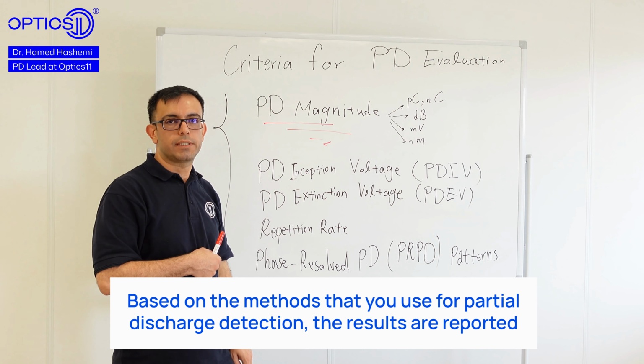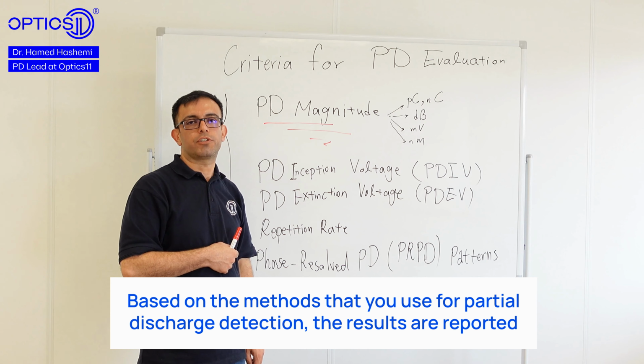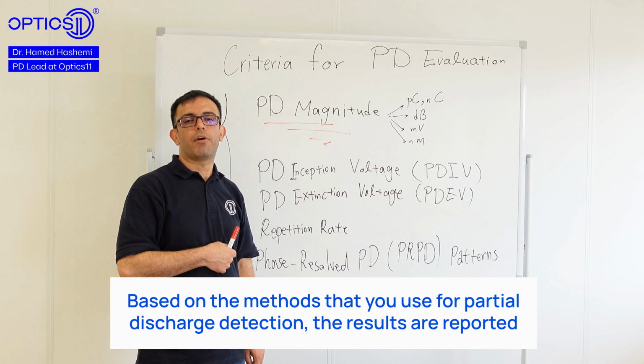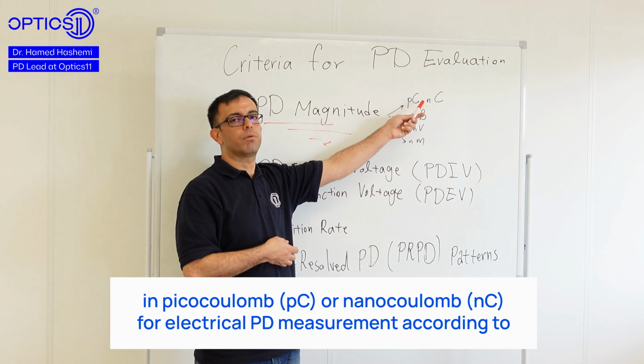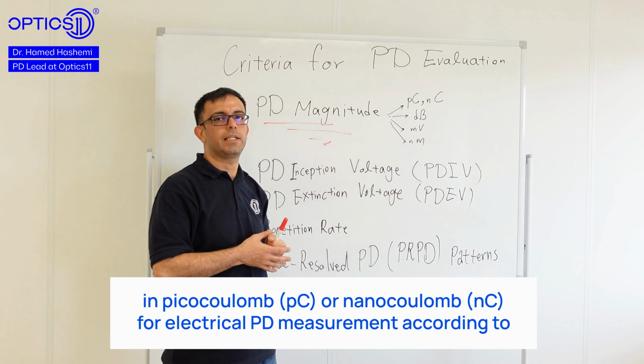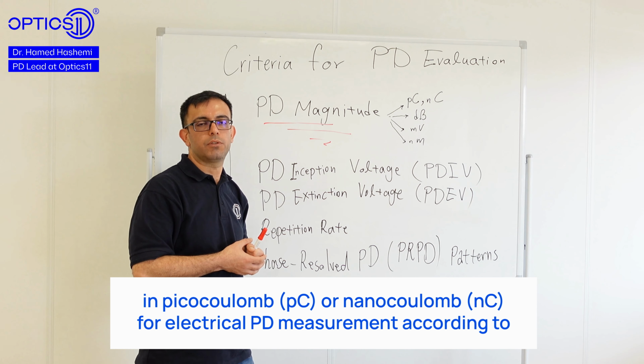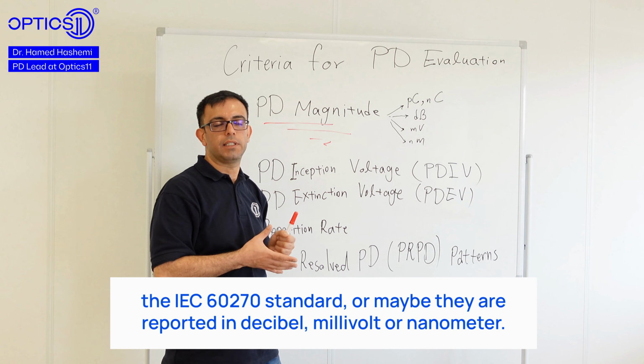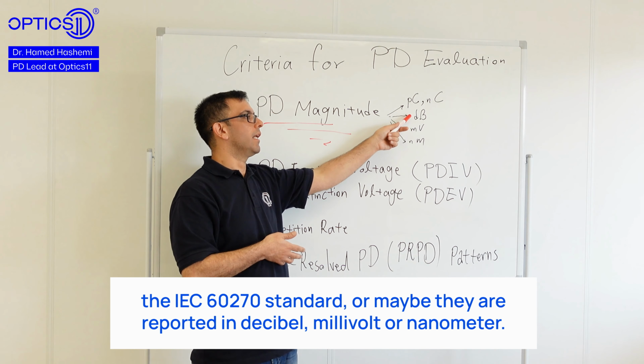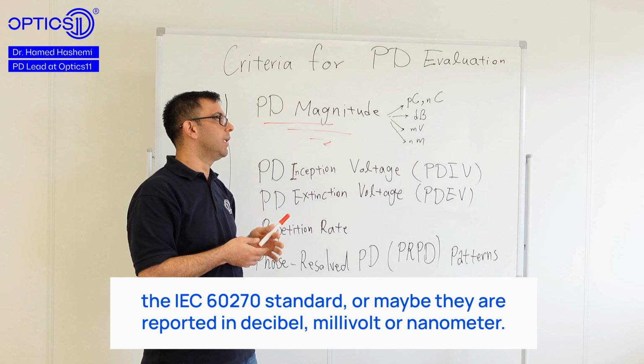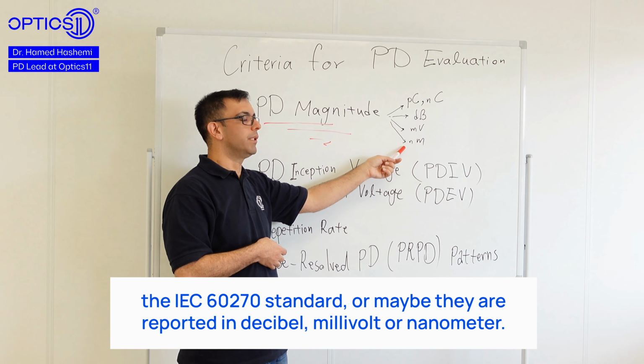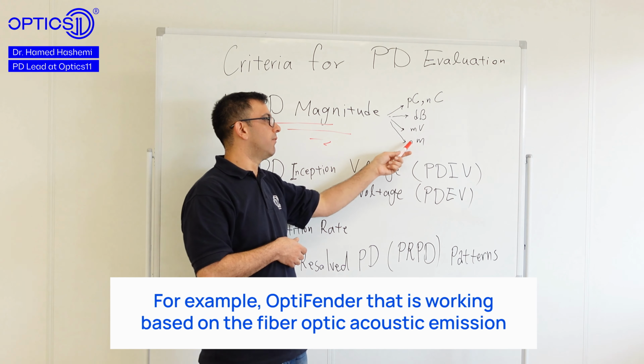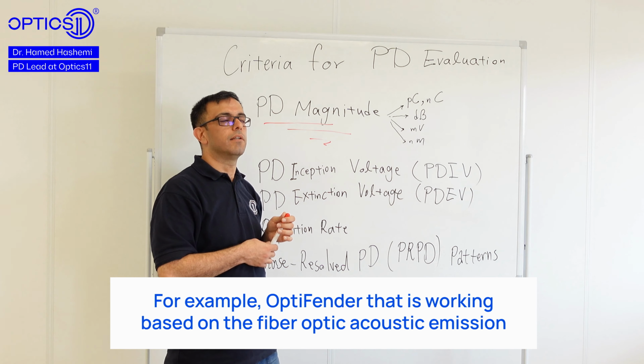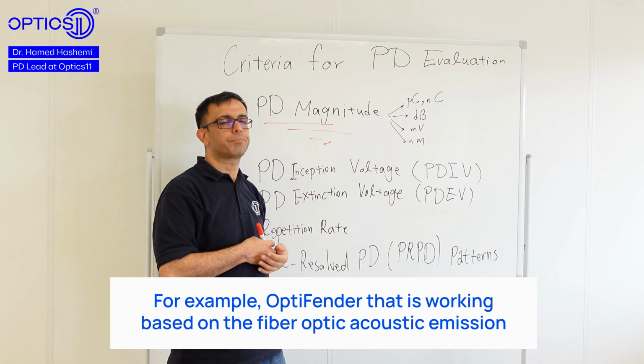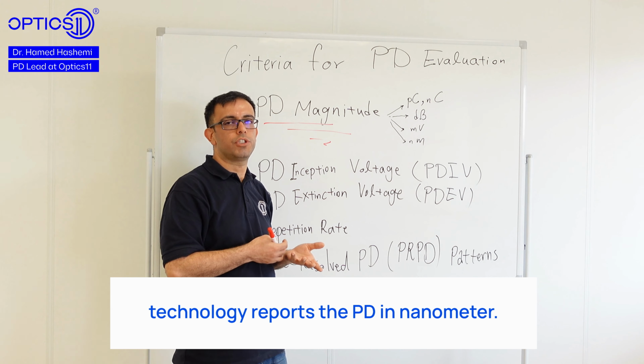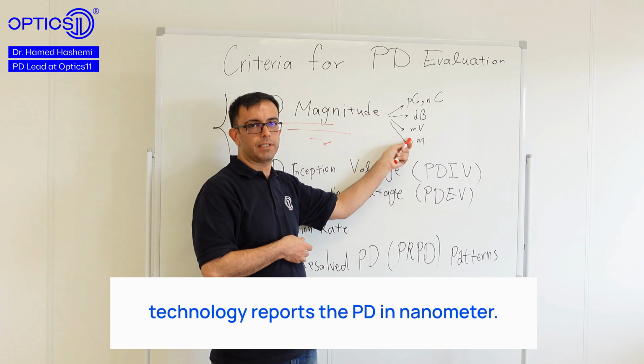Based on the methods that you use for partial discharge detection, the results are reported in picocoulomb or nanocoulomb for electrical PD measurement according to the IEC 60270 standard, or maybe they are reported in decibel, millivolt, or nanometer. For example, OptiFinder, which works based on the fiber optic acoustic emission technology, reports the PD in nanometer.